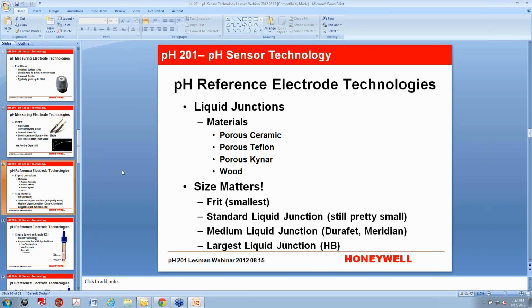And that's really a nice liquid junction for a laboratory type sensor, because a lab sensor goes into something nasty for just a few seconds, measures it, comes back out. So it's not likely to get damaged very quickly. But if you put something with a frit in the process, because it's one single small hole, it can get plugged up. But usually, more often, what happens is process fluid gets in there fairly quickly and kills your sensor fairly fast.